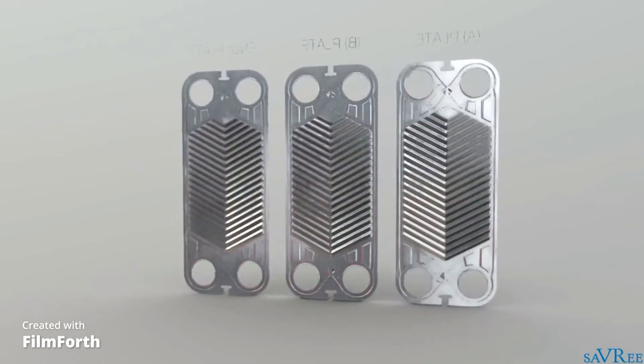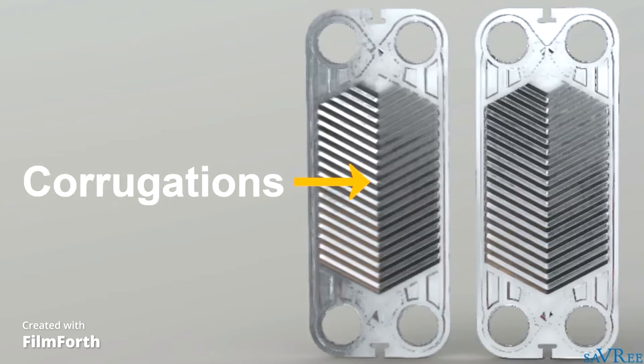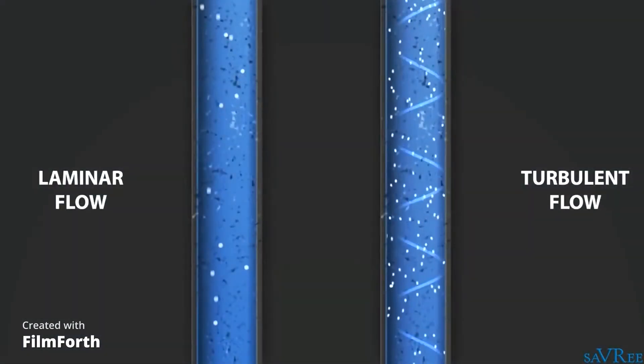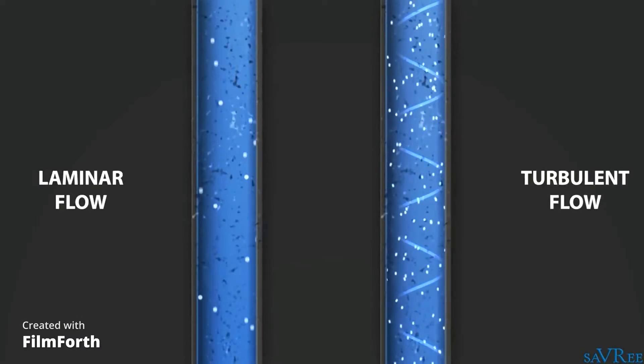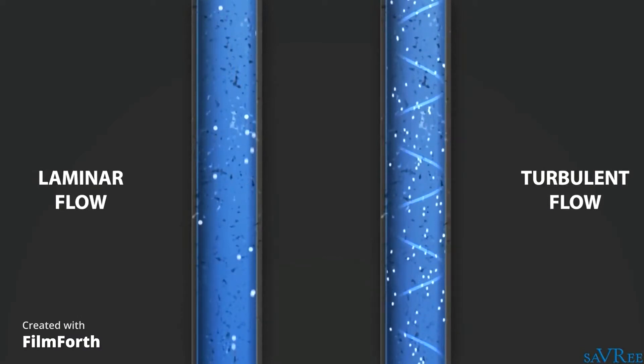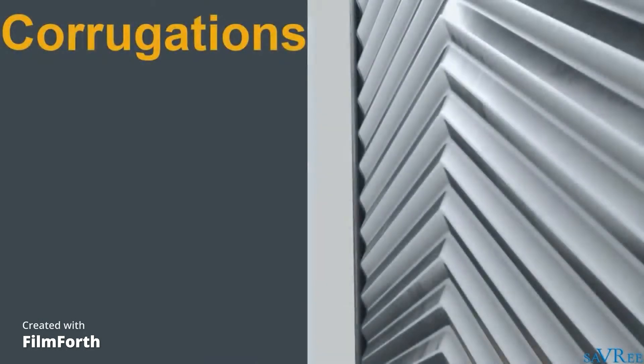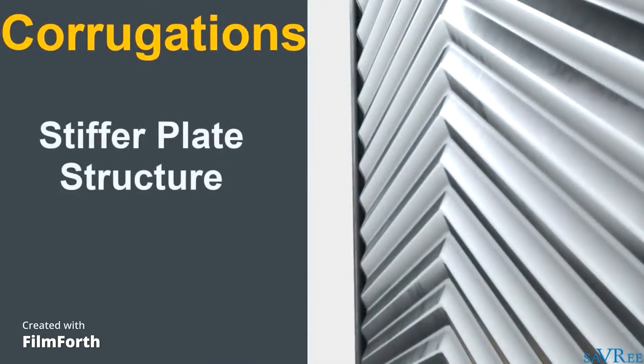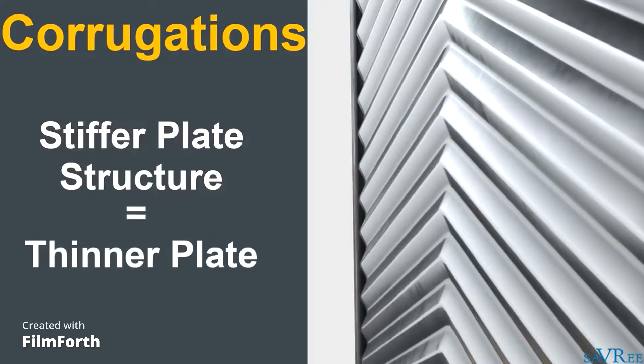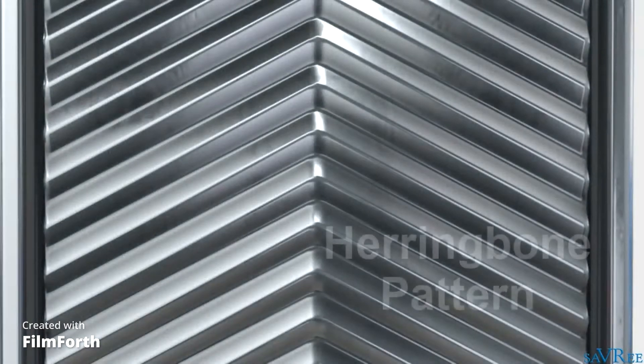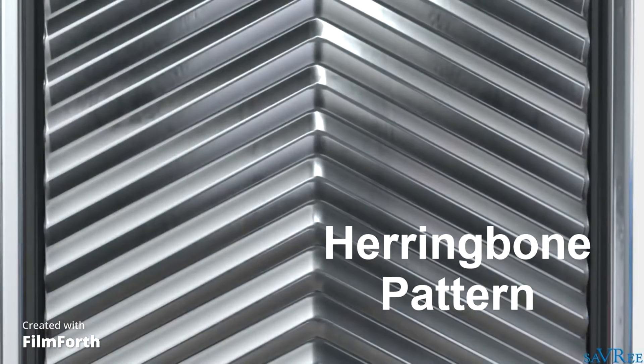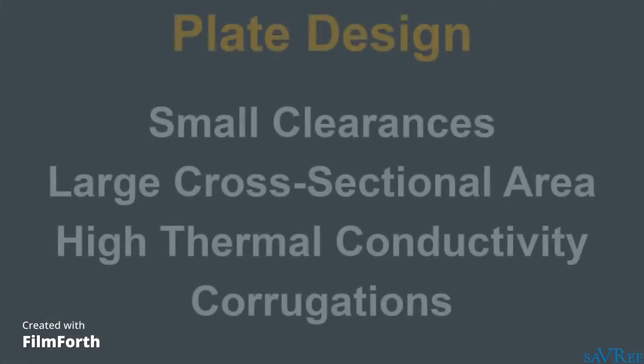Corrugations on the plate surfaces prevent laminar flow and promote turbulent flow, which increases the heat transfer rate whilst also reducing the likelihood of deposits accumulating on the plate surfaces. The corrugations also serve to stiffen the plate structure, which allows a thinner plate to be used compared to one with no corrugations. Note that plate corrugations are sometimes referred to as having a herringbone pattern. So although the plates look simple, a lot of engineering was applied to their design.